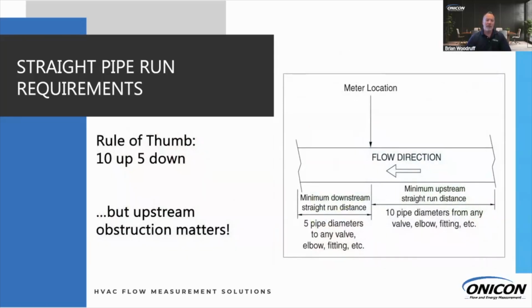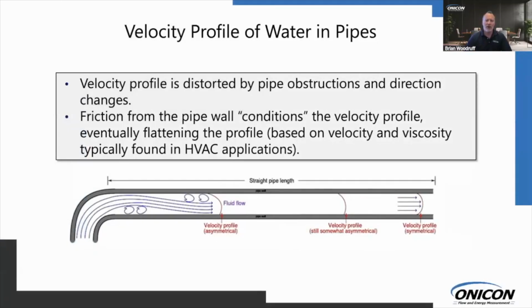So rule of thumb, and basically what you hear in the industry, is 10 pipe diameters upstream, 5 downstream. What that doesn't take into account is actually what that upstream or downstream obstruction is. Mainly the upstream is what we want to look at. So you see here the velocity profile. This is just an example of a 90-degree bend and seeing some of the swirls and the turbulence that takes place after that straight run. This is the basic example. And if you have that 10 pipe diameters, you see how the velocity profile is a lot more even. Then we're able to insert that meter in the pipe at an even average velocity profile.